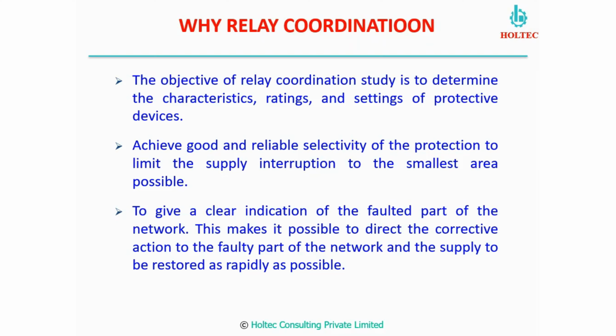if a fault, as in the previous example, is happening at F1, then for the F1 fault the device which has to operate is FU1, not R1 or R2. So this is the meaning of selectivity. We have to do the grading of the timing in such a way that first the fault will be cleared by FU1. If that is not done, then it will be taken over by relay 1, and ultimately if that also fails, then it will go to relay 2.